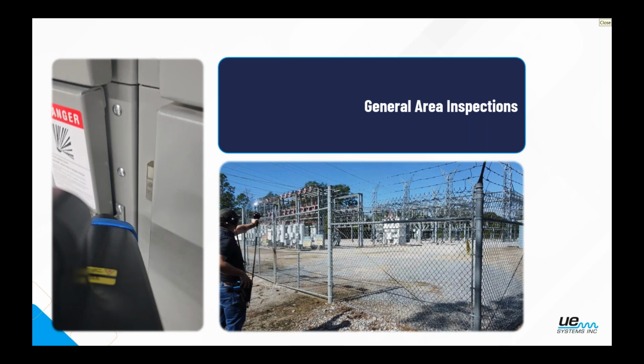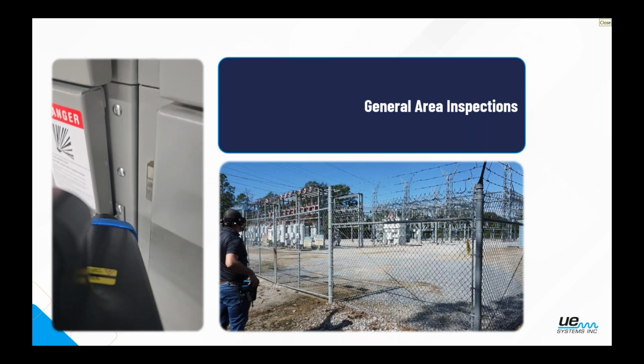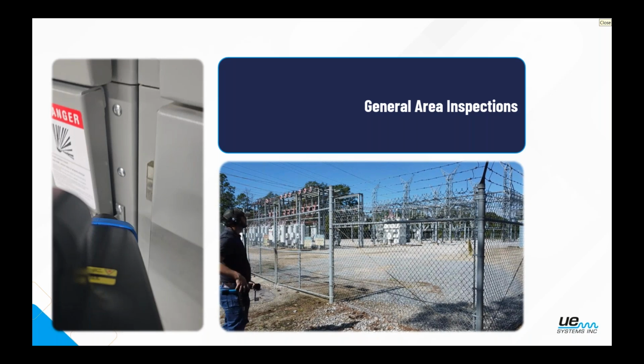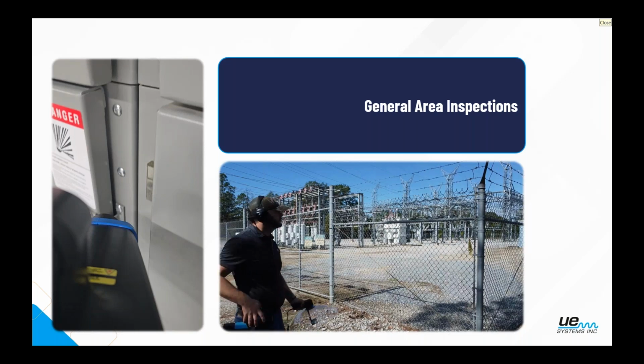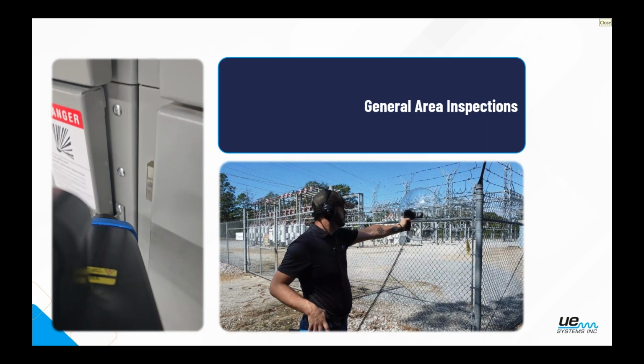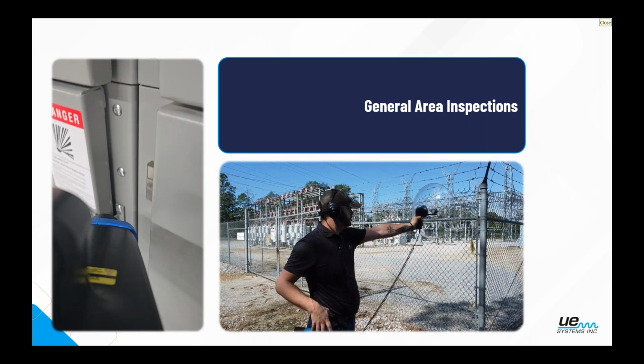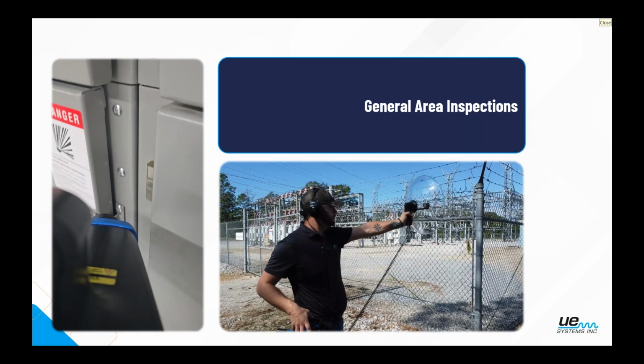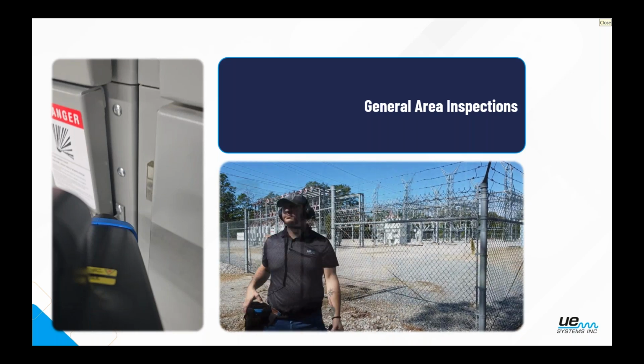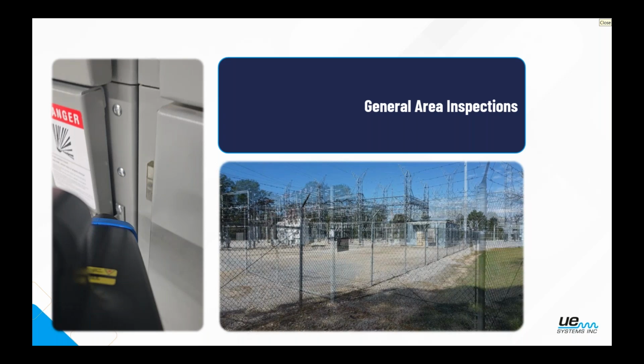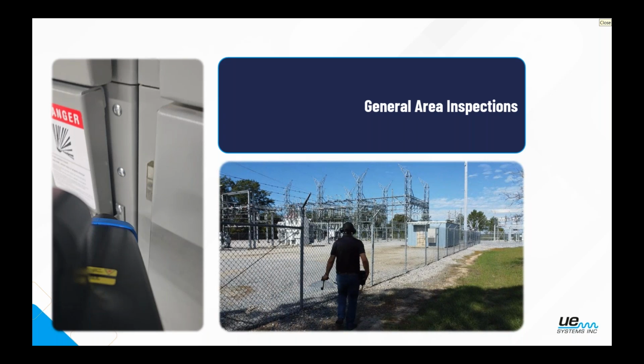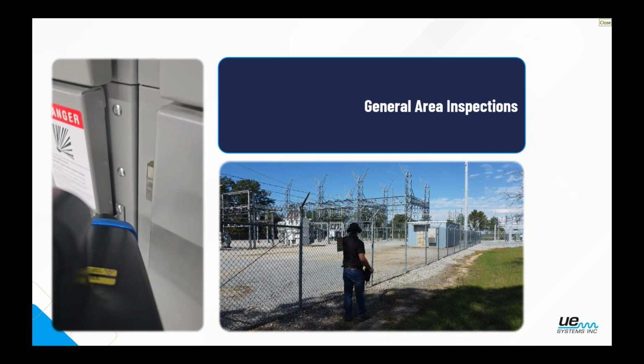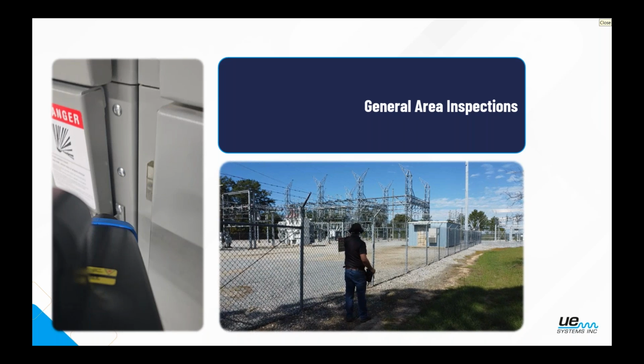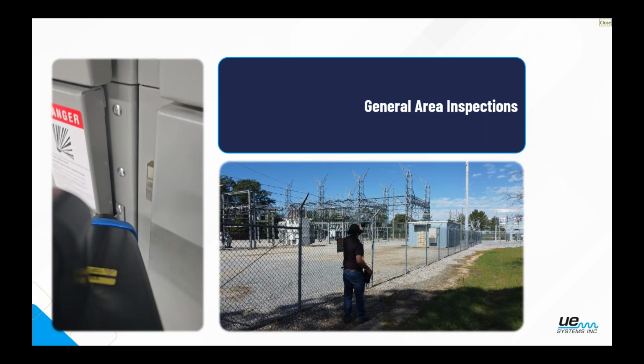Now, because ultrasound is so incredibly directional, it's strongly recommended to, once you inspect one area, go ahead and move around. Now, you can't see it off screen here, but there is a further area in the yard with a few more transformers. So rather than just staying in one point inspecting the whole yard, kind of shift to where I have that direct line of sight. And then to verify that I don't have issues anywhere else, moving around to another side of that fencing, re-inspecting one more time each one of those components to make sure that nothing was missed. And once again, be methodical, take your time. It's worth doing it right.